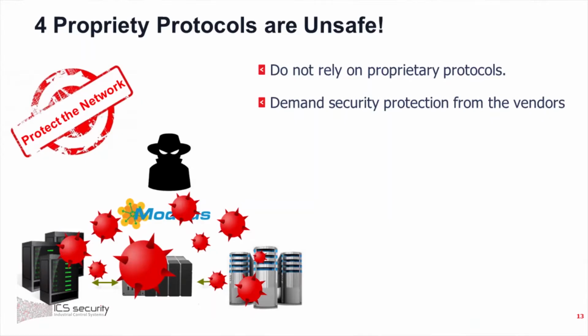We all know that Modbus protocol is commonly used between two vendors, two PLC vendors, for example. We also know that Modbus is the least secured protocol. So my suggestion is not to use Modbus at all, to use Profinet, to use OPC UA, or to secure Modbus if you must use it.